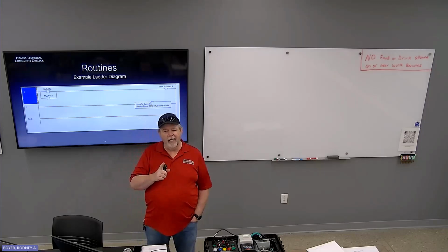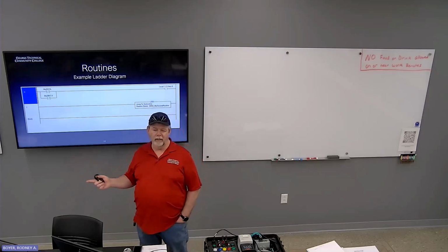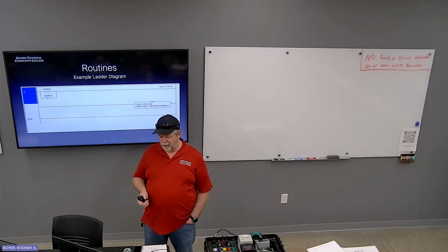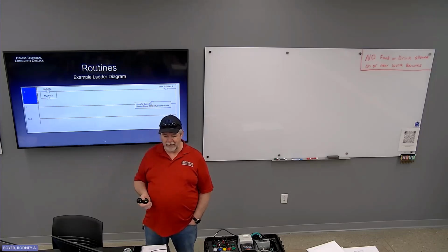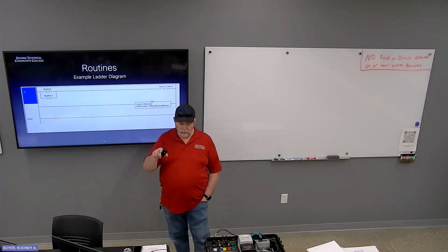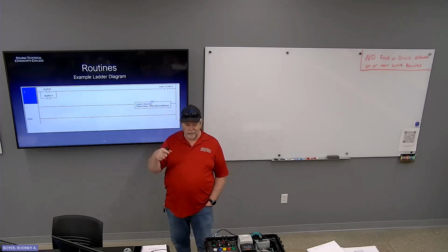The controller allocates 32 bits of memory. So if you have a whole bunch of bools in your program, then you just used up a whole bunch of controller memory that you didn't need to, because you can use one of the other data types and just individually address the bits in it.